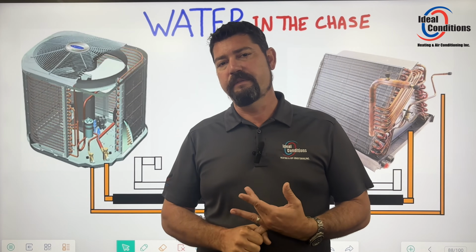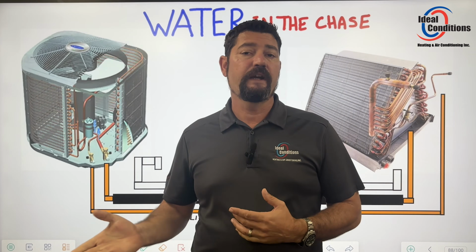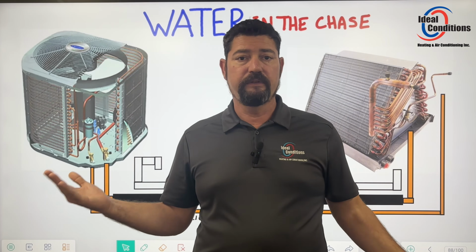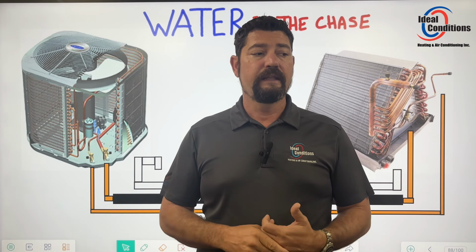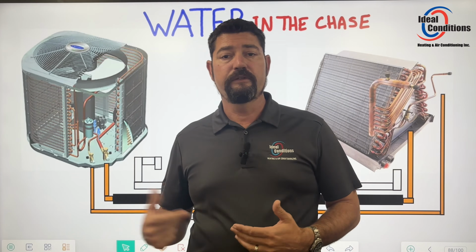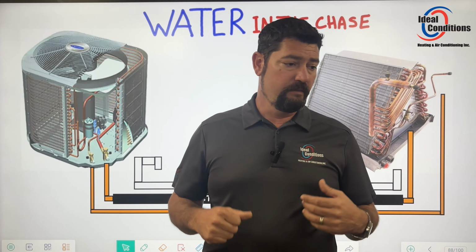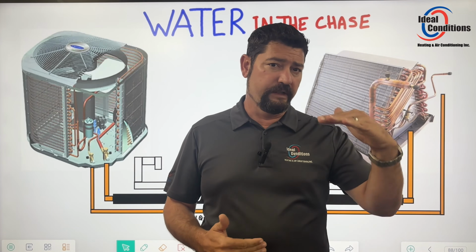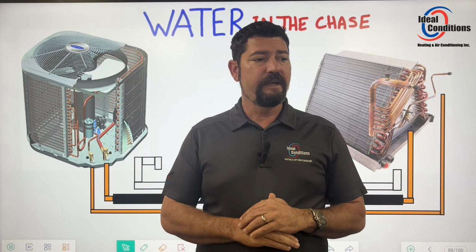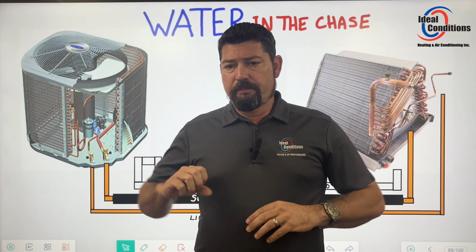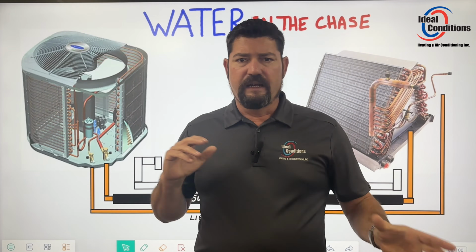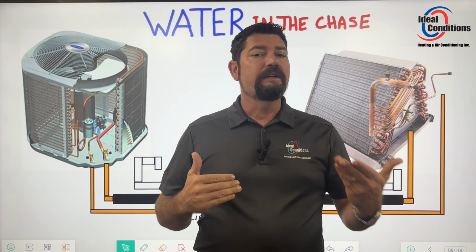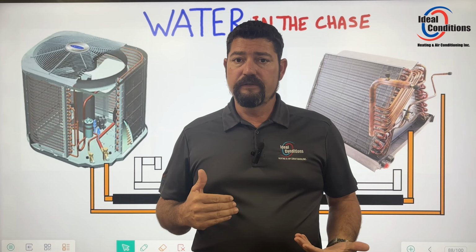Now your client might be spending money in the wrong direction fixing their issue. Instead of just insulating the copper pipes and balancing the charge right, they may be changing out valves that you're saying are bad that aren't. They may be paying for Freon that you're putting in the system to try to bring those numbers down. And you may say, by the time I added that valve, tweaked these charges, or added refrigerant, I did drop my superheat, because you're going to.